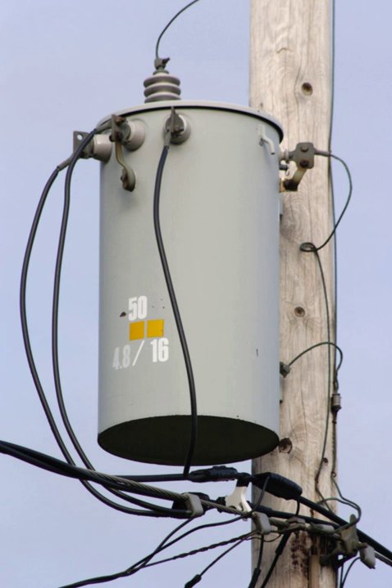Topic: Network configurations. Distribution networks are divided into two types: radial or network. A radial system is arranged like a tree where each customer has one source of supply. A network system has multiple sources of supply operating in parallel. Spot networks are used for concentrated loads. Radial systems are commonly used in rural or suburban areas.